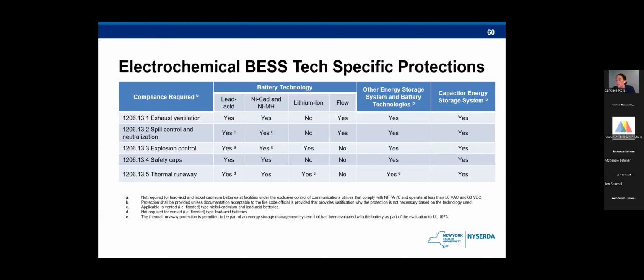So this table is showing the battery technology type, the chemistry, and is giving a glance of some of the protections that are needed for specific chemistry types. So there's different requirements based on the chemistry. And like I highlighted before, we're really seeing majority of lithium ion batteries coming into New York at this point. But you can see from the 5 different requirements, lithium ion only has to meet 2 of them: explosion control and thermal runaway. And we'll discuss a bit more why that is as we go through the slides.